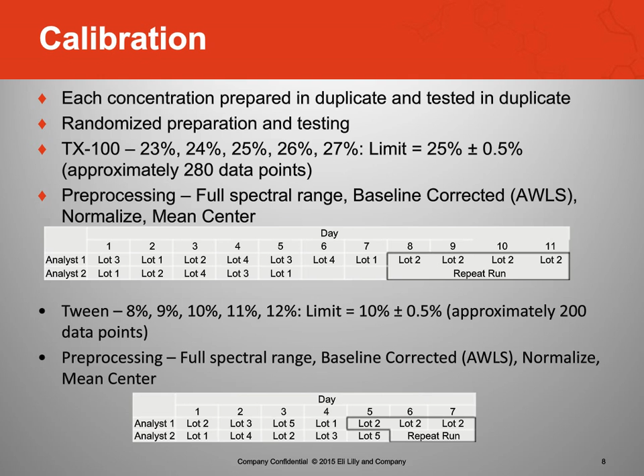One of the things I forgot to mention, but one of the practical sides of a portable instrument is you can do the validation in a laboratory setting and then pick up the instrument, and in our case a laptop, and carry it over to the manufacturing suite and do the method transfer. And so the examples I'm showing here are where we did the calibration in the laboratory, and then we did the method transfer in the production suite.